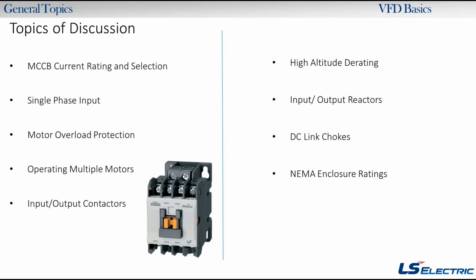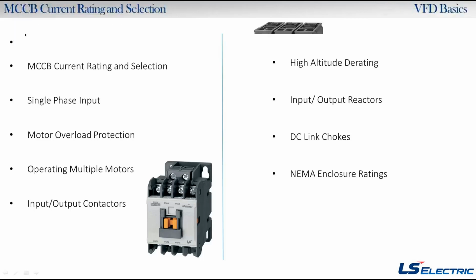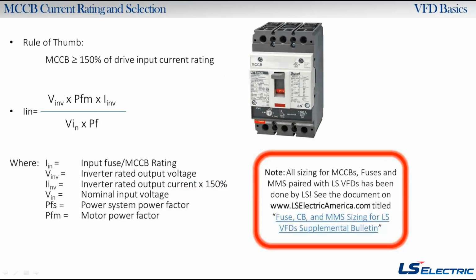So. All right, the first thing is one of the more important accessories or peripherals that goes with a drive. It goes in front of it, which is a molded case circuit breaker. We just call them MCCBs for short, or you could put a fuse or whatever in front of it. Generally, the rule of thumb for a circuit breaker in front of a drive is that the MCCB is going to be equal to or greater than 150% of the drive input current rating. So you could find that.